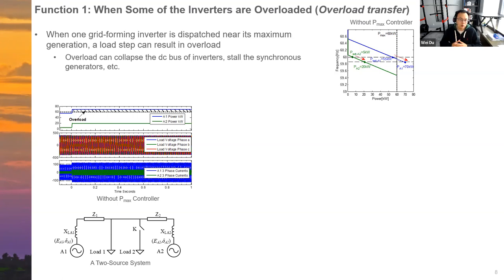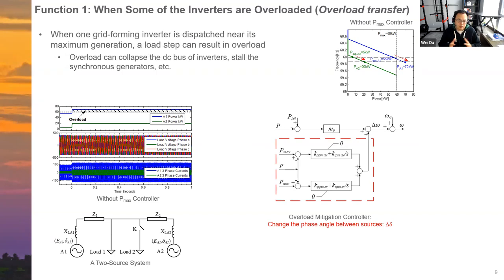So this overload will cause issues, maybe collapse the DC bus of the inverter or stall a synchronous generator. So we need to solve this overload issue. For the CERTS microgrid, as I mentioned, they use this very simple anti-windup PI controller to solve this overload issue. The key concept here is that once P exceeds Pmax, this controller will be activated to reduce the frequency of this A1 inverter rapidly. And by reducing the frequency, we can change the phase angle between these two inverters. So this can redistribute the power flow between the two inverters.